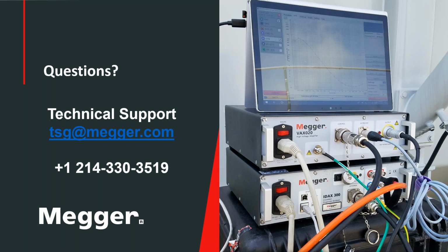All right, thank you. Dr. Robolino, what are the assessment limits taken from? That is a very good question, because there's lots of information in different standards talking about the limits of moisture in the liquid insulation and how those are correlated to the insulation through equilibrium curves, for example, in the paper insulation. So mainly, if you look into the standards, none of those is directly talking about moisture in the solid insulation.